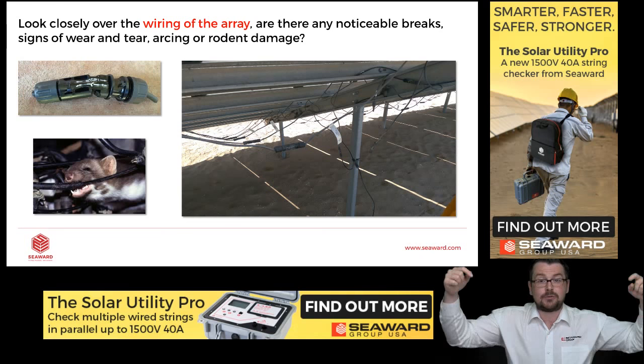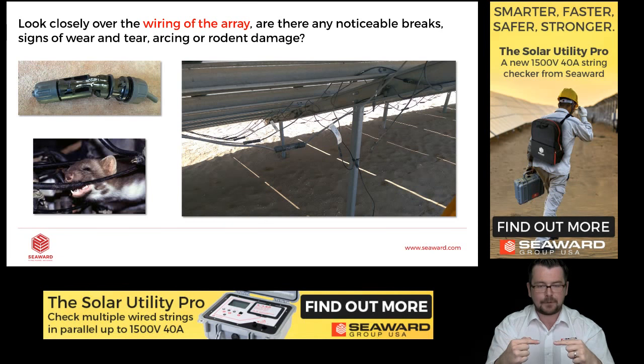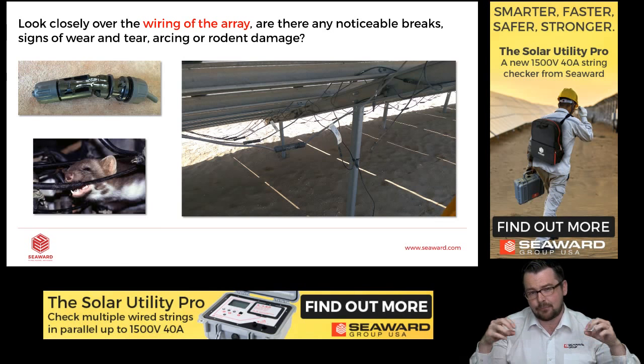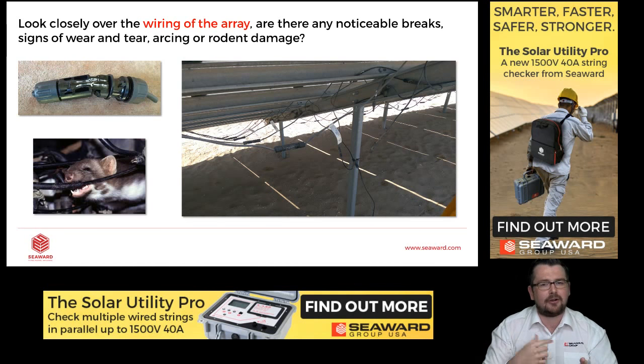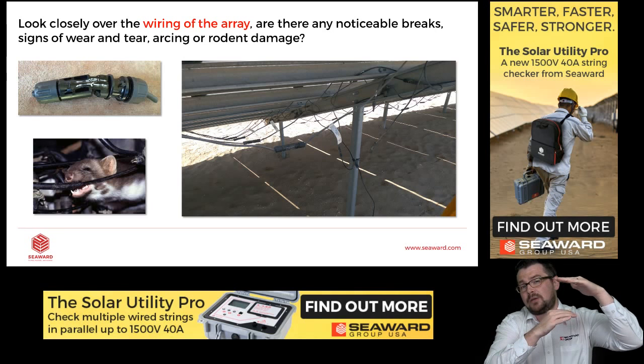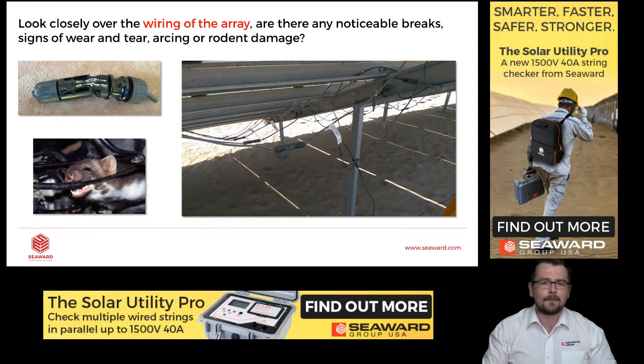if the cables are like this means when it rains, the water is going to run down the cables and go into the MC4 connections. And what will happen there, we'll get an insulation fault, and we could potentially have arc faults if it's affecting the connection. And I've seen this also in the field, we've had users go out and test in the morning after it's been raining and it's been very wet, and that moisture is inside the connection. They run a test with their instrument and they get a low insulation resistance. Then they go back later in the day and retest, and the insulation resistance is fine. We get a good level of insulation resistance. What's happening there is the moisture in the cables is actually drying during the day. So this is a very big problem.